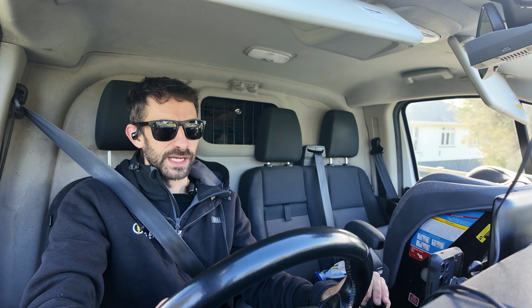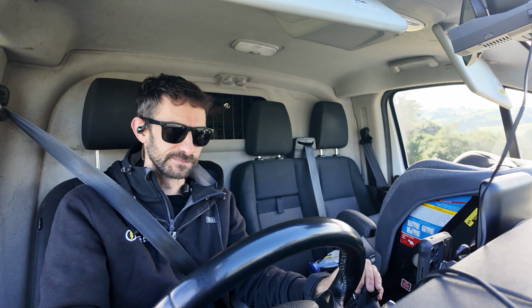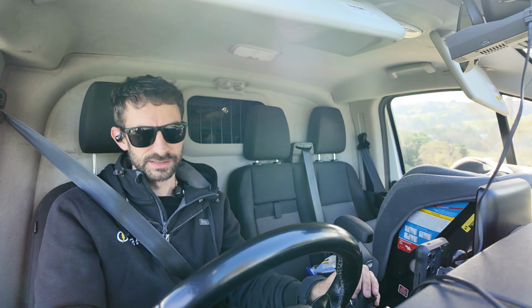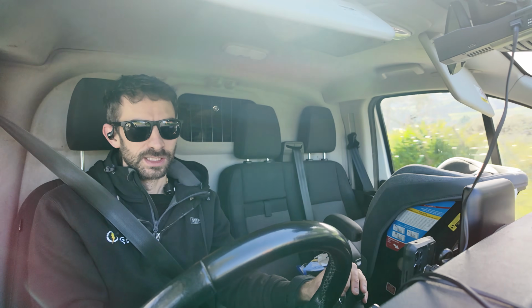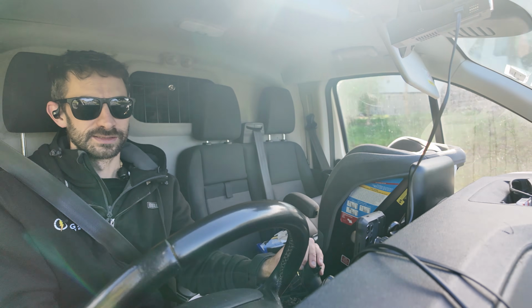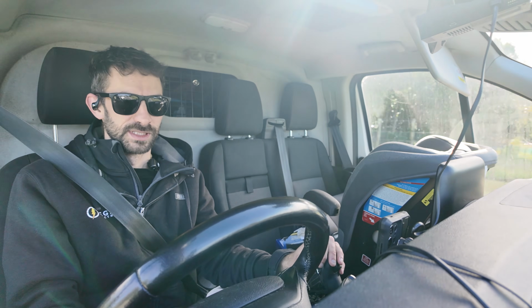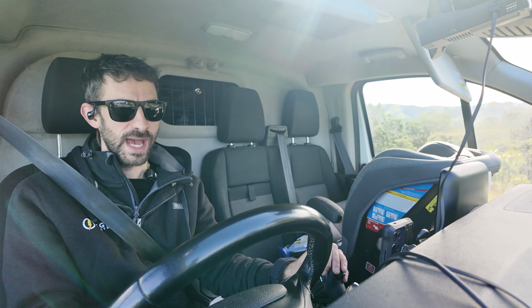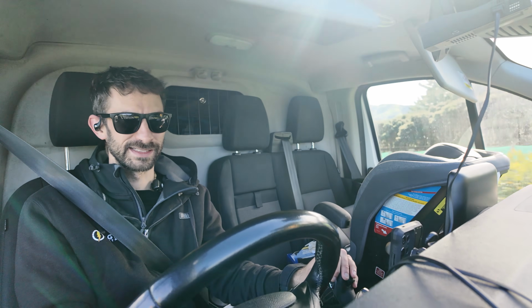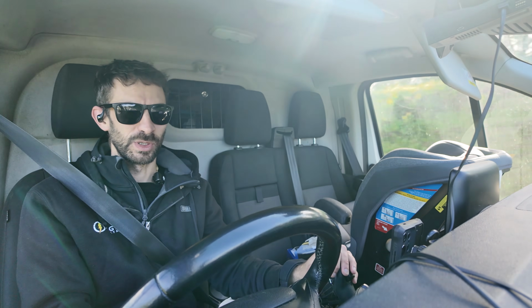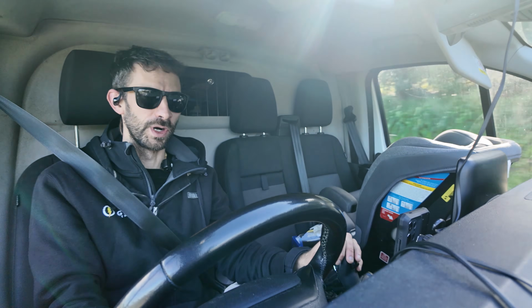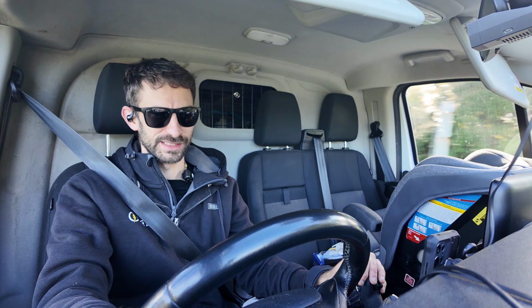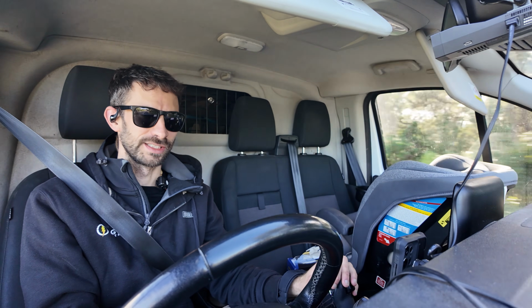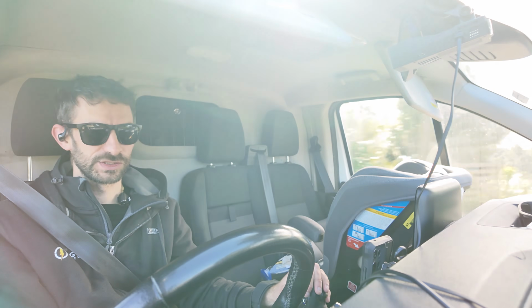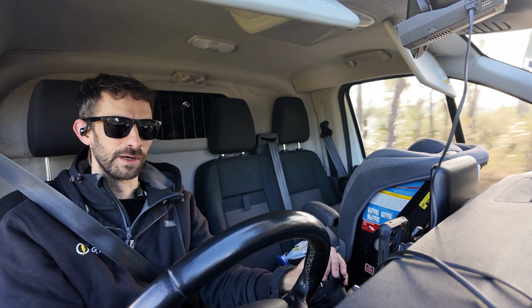So that's one reason why you can't have a completely isolated installation. Isolating one piece of equipment is not the same as isolating a whole installation. Another reason is because when you have a transformer, you have to earth the transformer, because otherwise you can get stray voltages building up where the potential difference between the transformer and earth becomes quite high, and then you get discharges, and those discharges can damage equipment and be dangerous. So you have to earth the transformer.